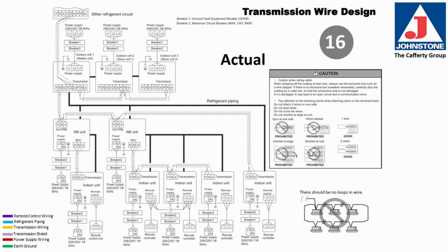Transmission wire design. When you're stripping insulation from the lead wire, always use a wire stripper or such tool. If there is no wire stripper available, carefully strip the coating off of the wire using a cutter so that you don't damage the conductive wire in the center. If the wire is damaged, it may lead to an open circuit and a communication error.